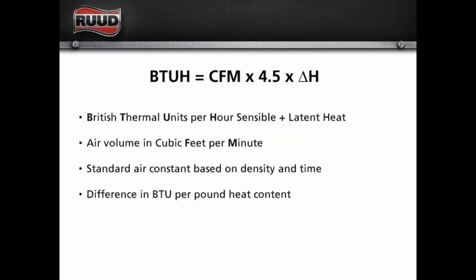Write this down. It'll be on the handout, the sheet that I'm going to email. But go ahead and write this down. So BTUs per hour equals CFM times 4.5. 4.5 is a constant in this formula. We're always going to use that. Times our delta H. And the delta H is the difference in enthalpy, right? So BTUs per pound of heat, right? British thermal units, and that's how all of our units are rated, right? And BTUs per hour.